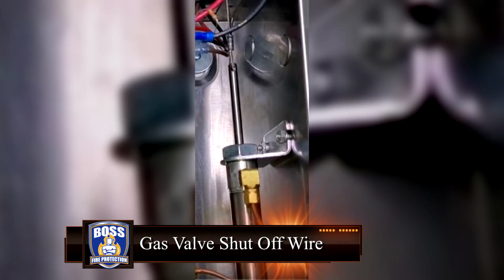This is the gas valve shutoff wire that comes down on the right side of the micro switch into the air plunger. This line is installed with hand-tight tension and set off by the compressed air released by the cartridge. This shuts off all gas under the vent hood when the regulated release is triggered, eliminating a potential source of fuel if there is a fire.